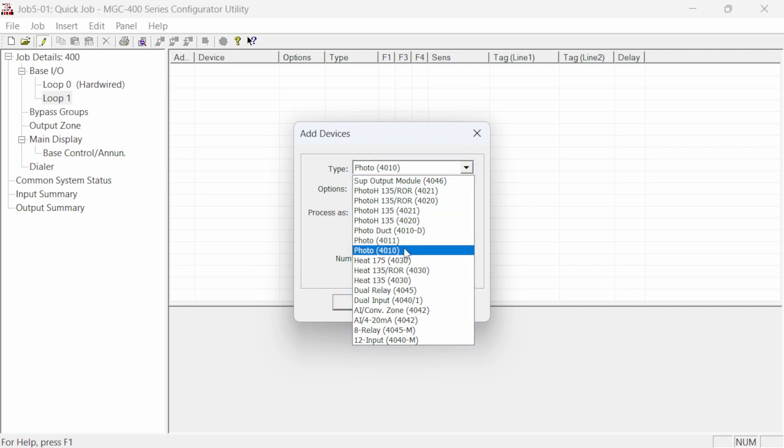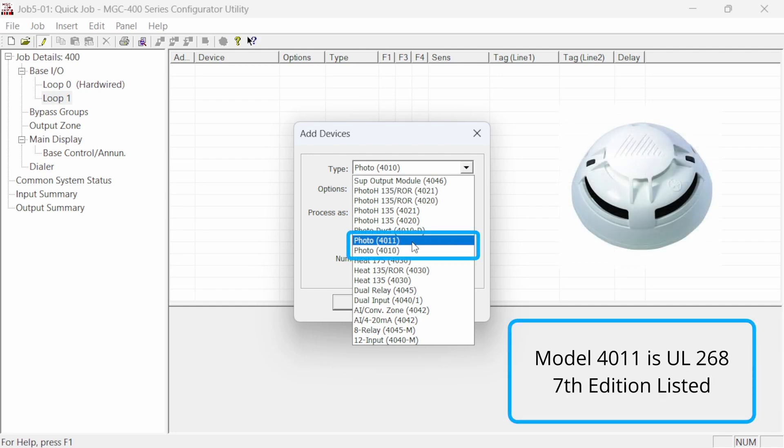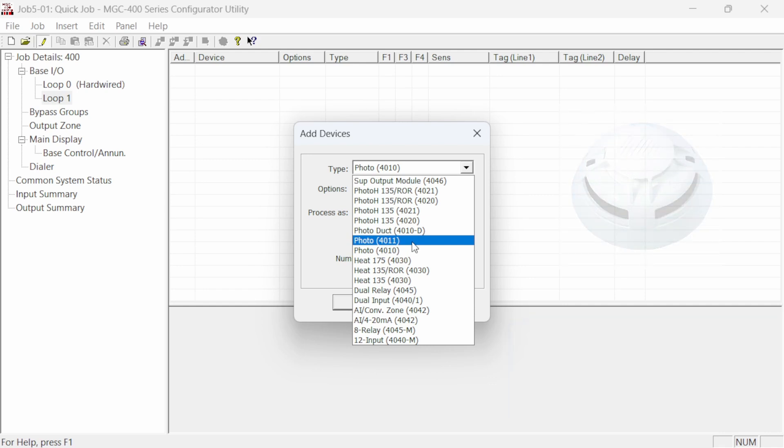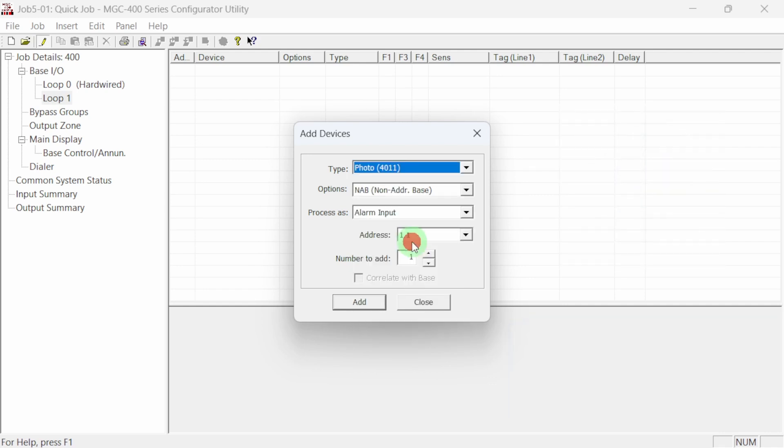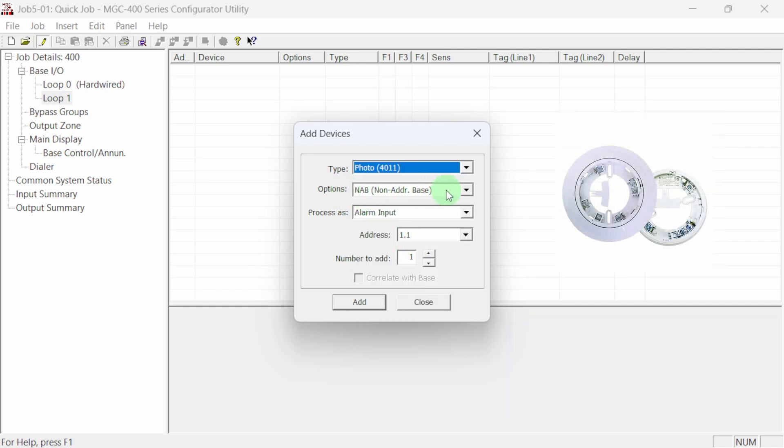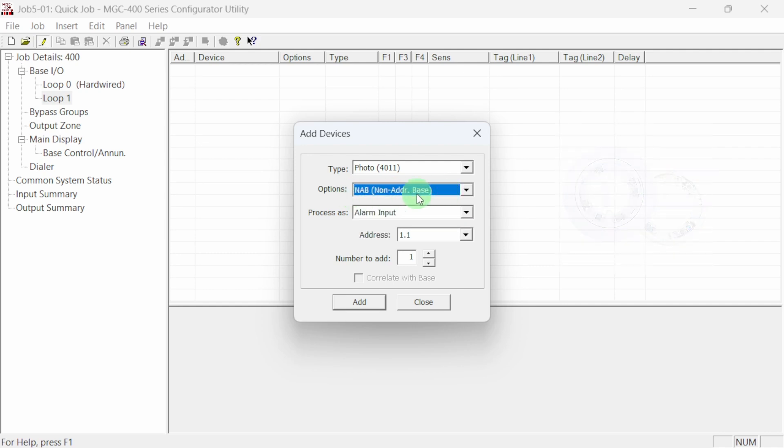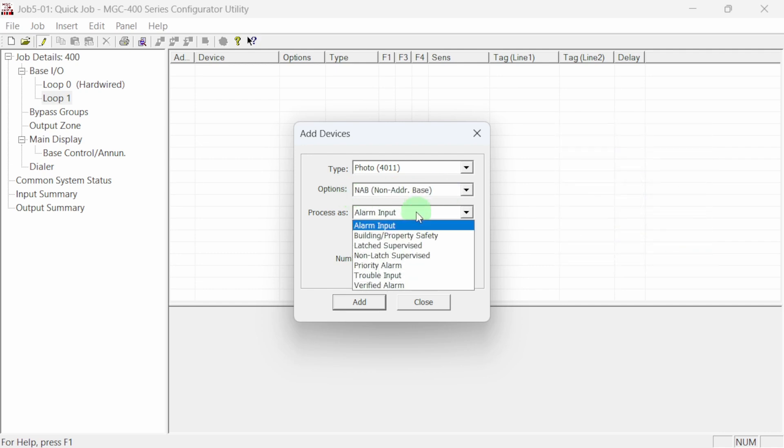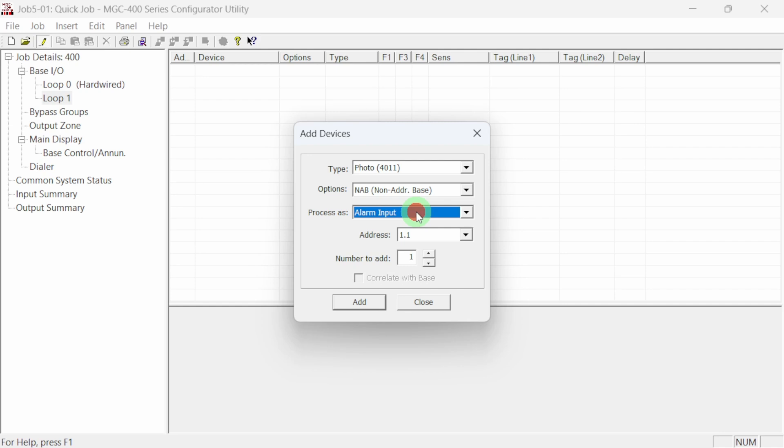The photoelectric smoke detector devices have two model numbers, the older 4010 and the newer 4011. Choose the model number you will be using on your job. Next, choose the type of mounting base for the smoke sensor head. Here we will choose a standard non-addressable base. Now, select how the device will be processed by the system when activated. For our smoke detectors, we will select alarm input.